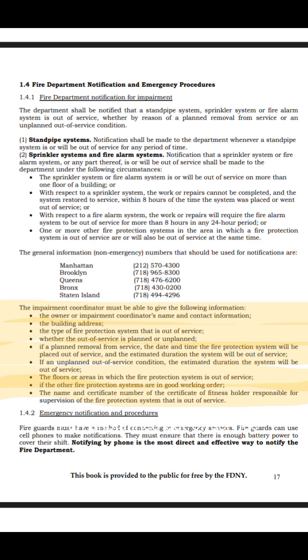If an unplanned out of service condition, the estimated duration the system will be out of service. The floors or areas in which the fire protection system is out of service. If the other fire protection systems are in good working order, the name and certificate number of the certificate of fitness holder responsible for supervision of the fire protection system that is out of service.